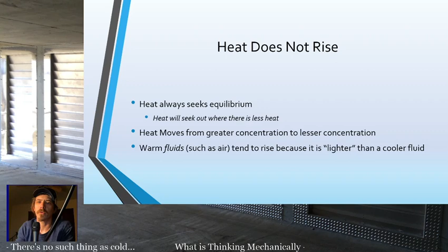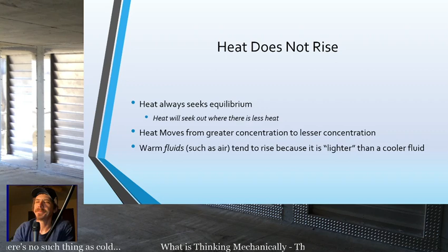Heat does not rise. Heat seeks equilibrium, moving from greater concentration to lesser concentration. But it's also important to understand that warm fluids do rise, because when you're talking about something like a water heater with a broken dip tube, and you're not feeding the cold water to the bottom, even though that whole heater will get warm, that cold fluid will short cycle. If you don't understand that short cycling is occurring, you might think something else is going on because the cold fluid is bypassing. Maybe that's not the best example, but both things are important to understand.